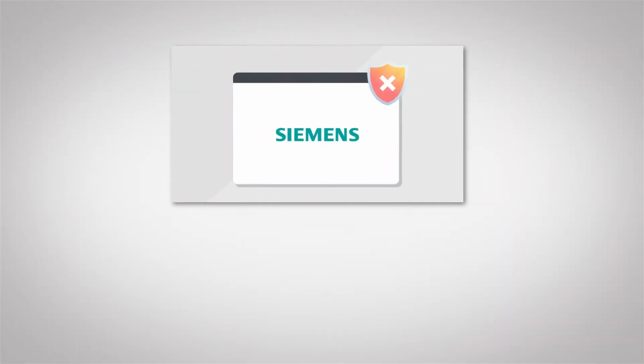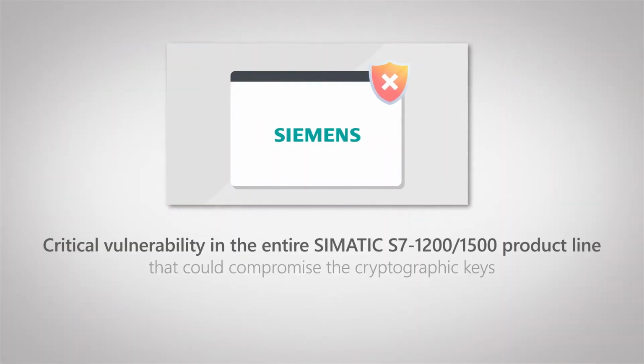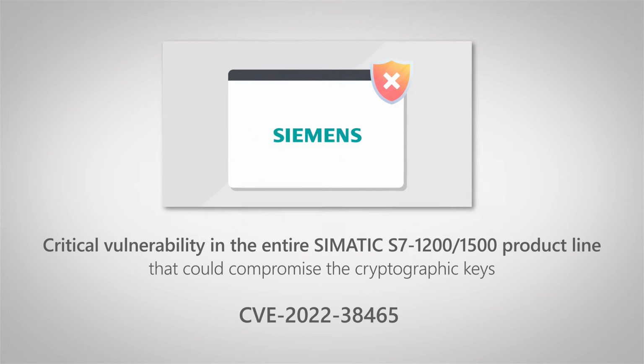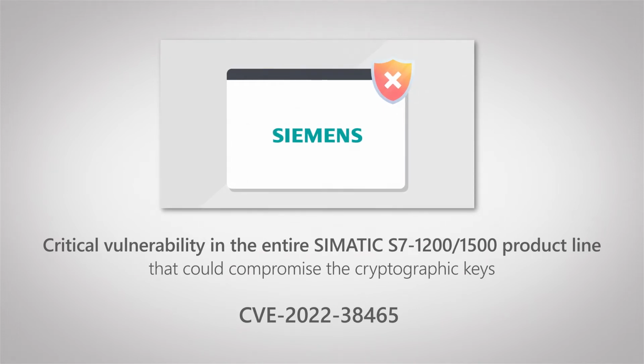Siemens recently released a new security advisory for their SIMATIC S7-1200 and 1500 PLC models. This vulnerability is in reaction to a weak key protection vulnerability that has a high CVSS base score of 9.3. Obviously, due to the high CVSS base score, you know that it's a critical vulnerability. So it's important that you take a look at your Siemens PLC devices and ensure that they're on the latest firmware version, or at least that you've applied mitigations for this specific vulnerability.